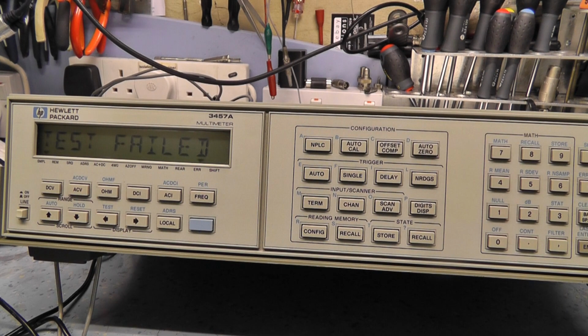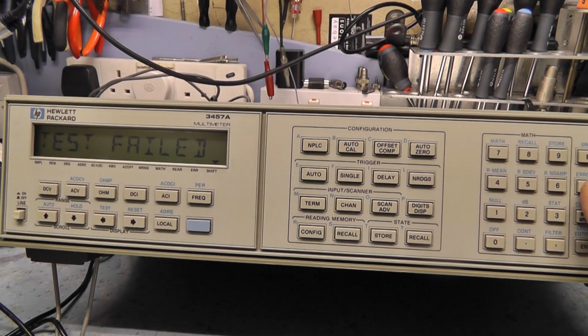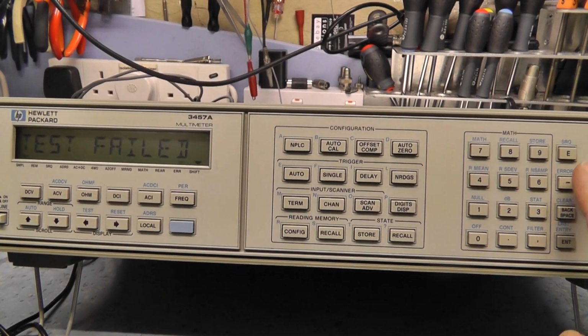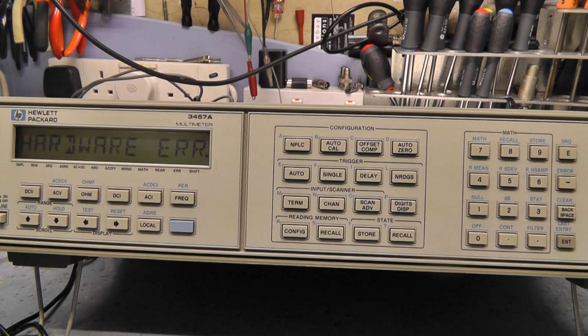Now the procedure for that, it says, is to run an instrument self-test: press the blue shift key and the test key, which is what I've just done. The display will show testing, and it takes about 7 seconds to complete. It says if the display shows test failed, check the error message by pressing the shift key and the error key. So that's the shift key, and that's the error key on the right hand side, just out of frame. I'm trying to get it all in frame, but it's a bit difficult, but there we go - it says hardware error.